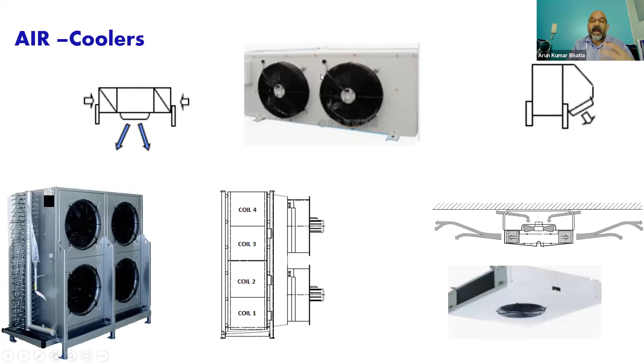For example, in third-party logistics warehouses, many rooms work in dual temperature. There we should have an evaporator with a higher circulation rate, and we can control fan speed. So for chiller application in our example, these fans should generate 15,000 meter cube per hour volume for frozen food storage, and 25,000 meter cube per hour for chilled storage food application. I hope this is clear.